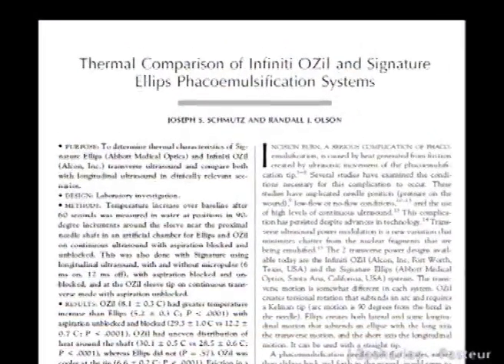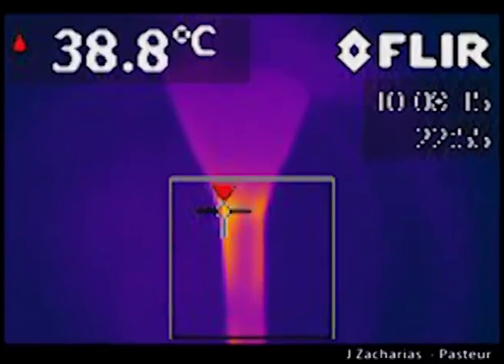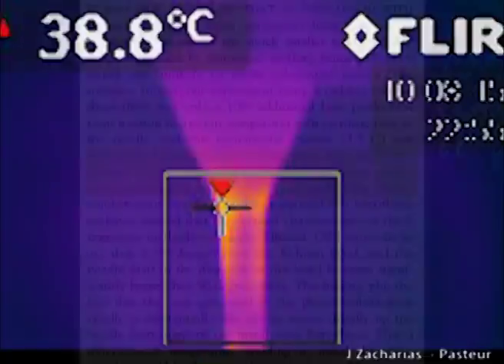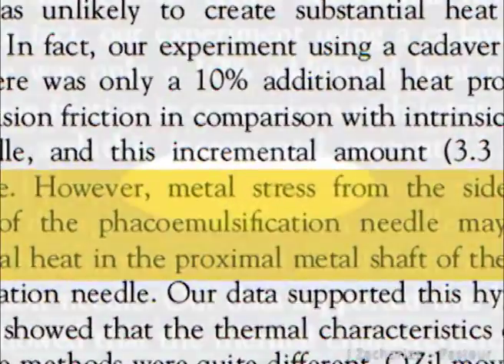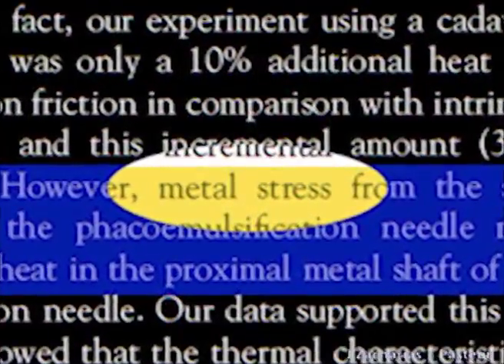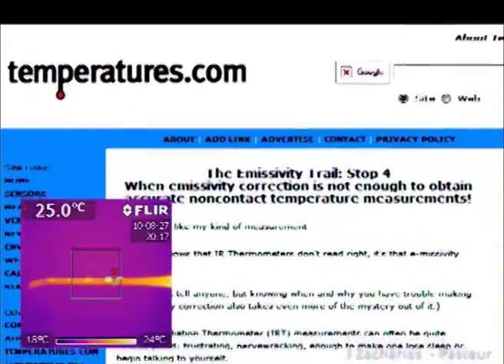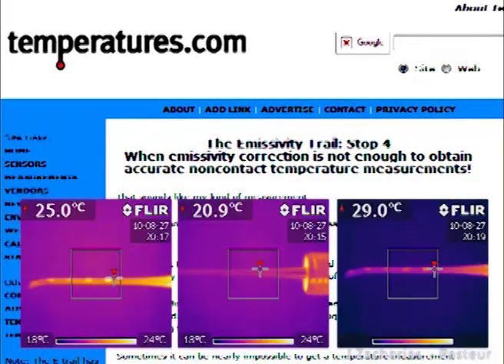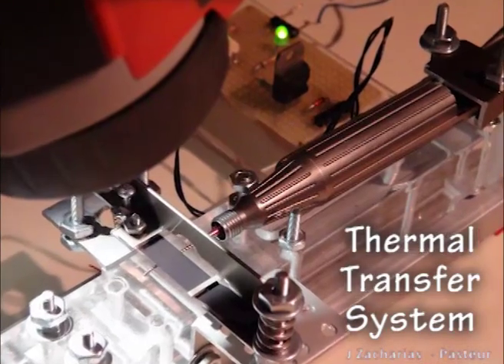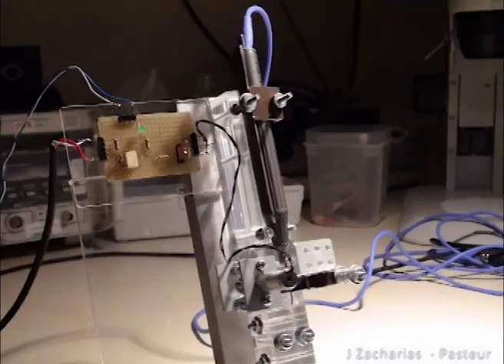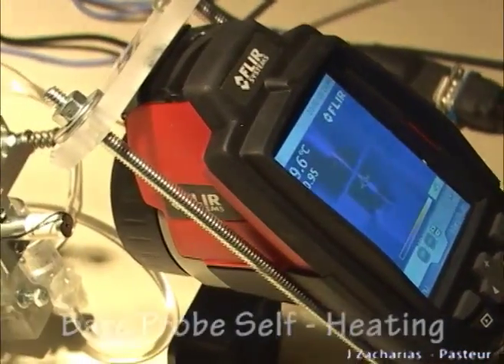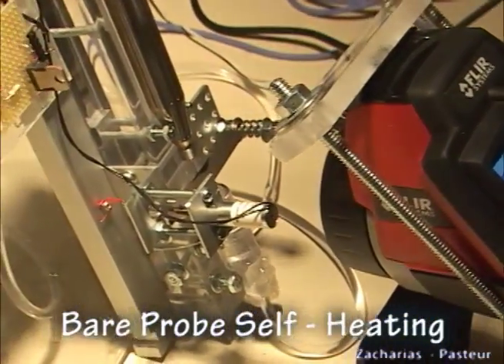However, some have suggested that warm zones seen with torsional at the back of the sleeve are produced by heating of the phaco probe by internal metal stress. Bare probes have very low infrared emissivity, making infrared imaging inaccurate to explore this theory. We designed a thermal transfer system to examine bare phaco probes in search of zones of self-heating by ultrasound.